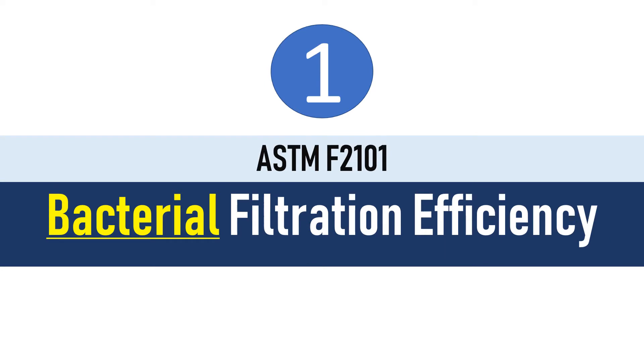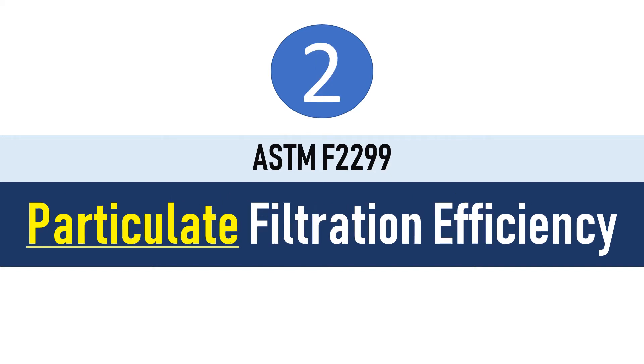The first requirement of materials intended for use in medical face masks is bacterial filtration efficiency, tested according to ASTM F2101. The second requirement is particulate filtration efficiency, tested according to ASTM F2299.